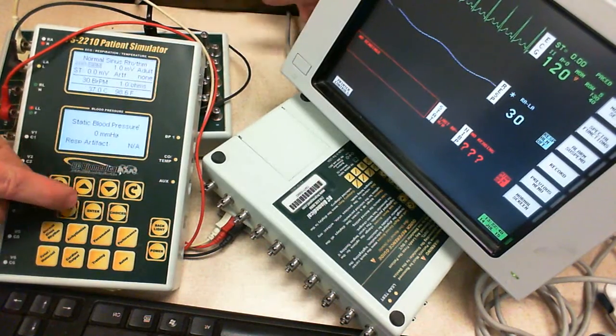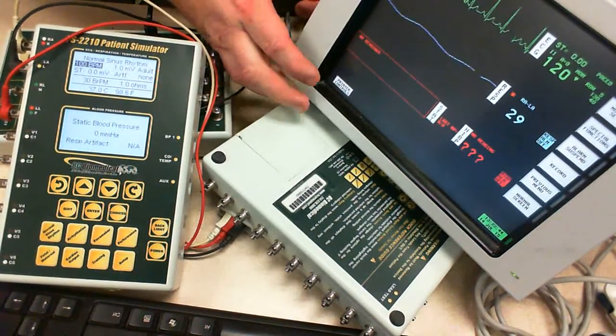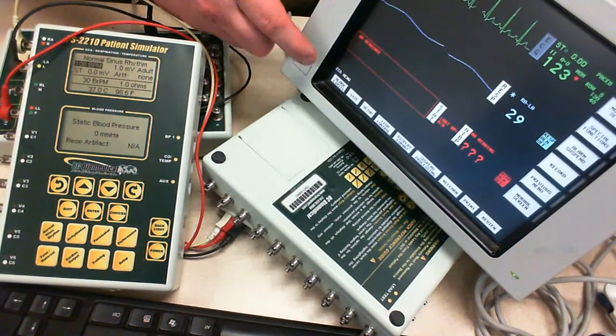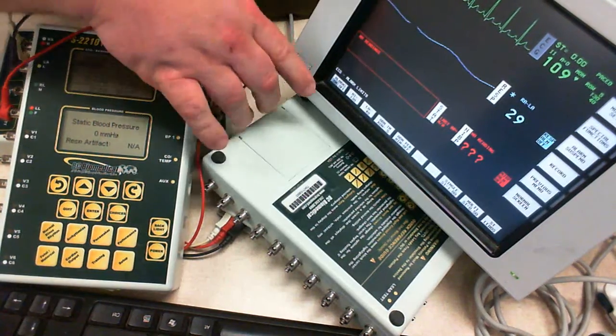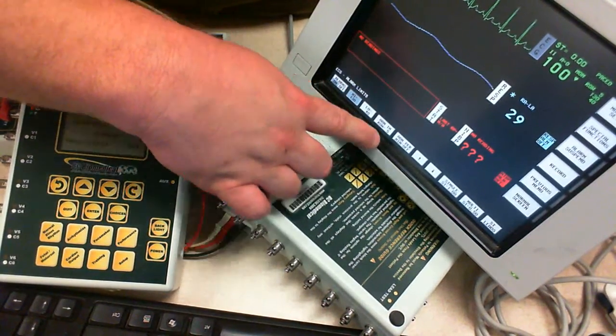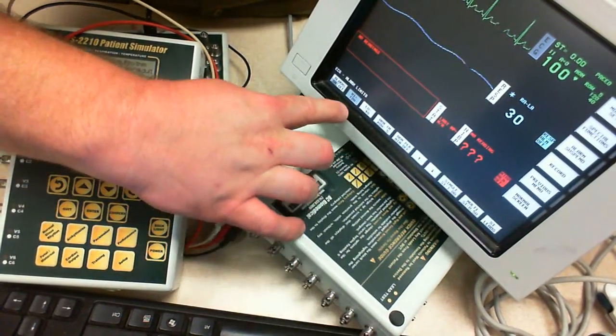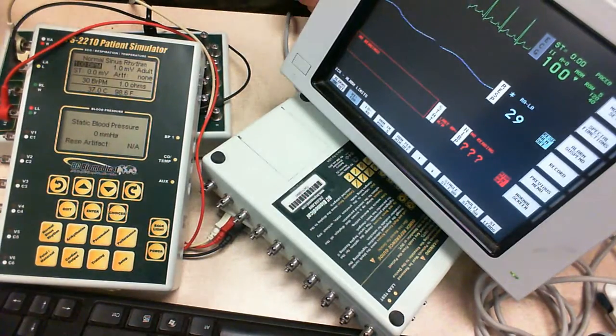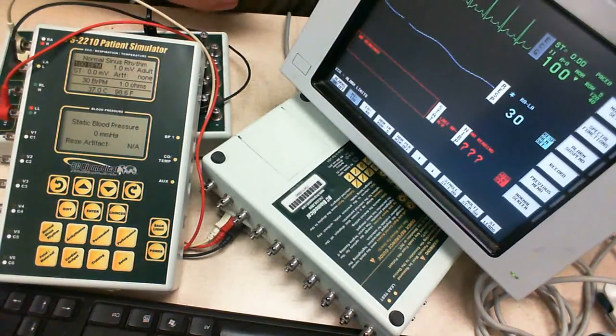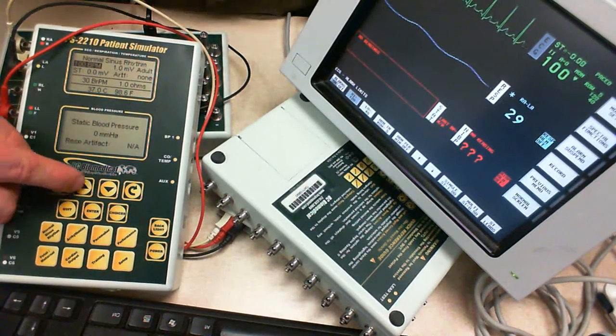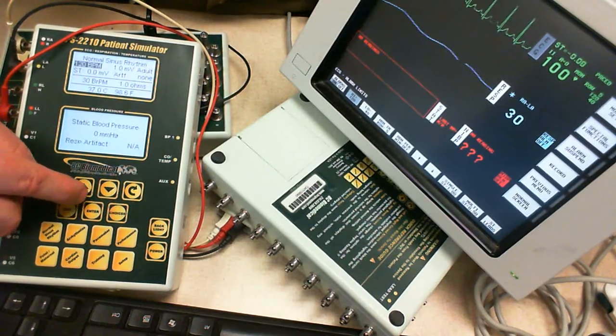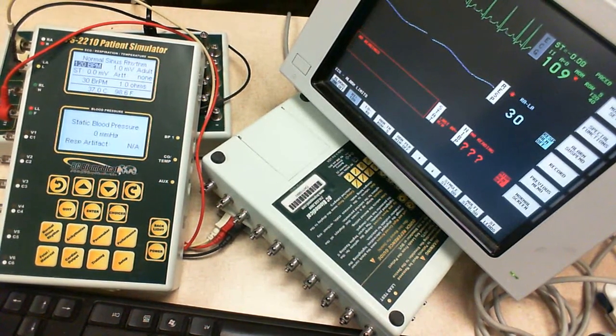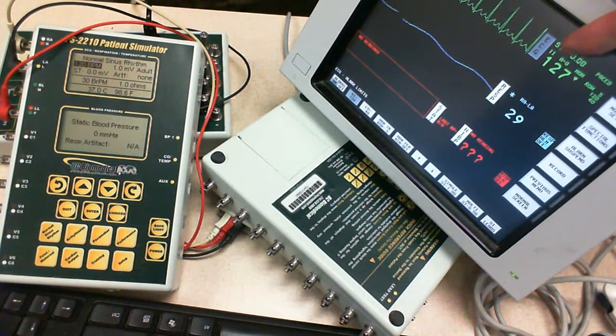What I'm going to do here is drop my ECG down to 100. I'm going to go into my rate alarms. You press ECG. Down the corner here, it'll say alarm limits, and then you have an option here. I'm going to go to my high alarm, and I'm going to lower it to 120 as requested, right? I believe we can trigger it right there. Notice how in the corner here it has adjusted to 120. So I'm going to go back over here and raise my heart rate to 120. After this goes above 120, we should be able to see an alarm. Let's see. Watch it not trigger here.